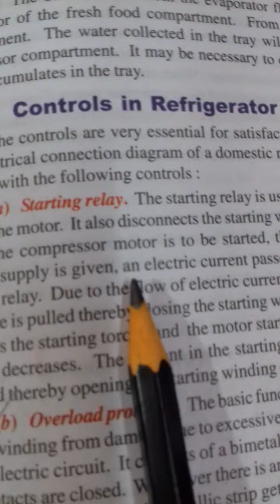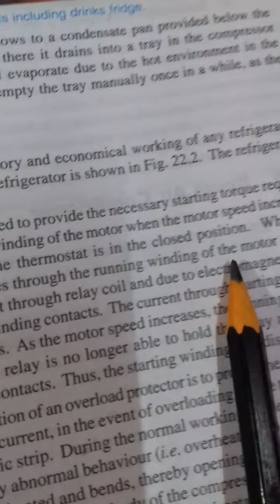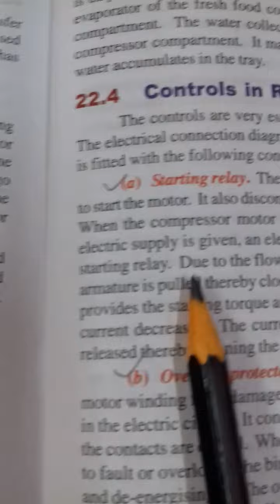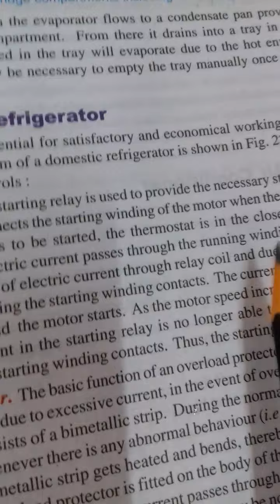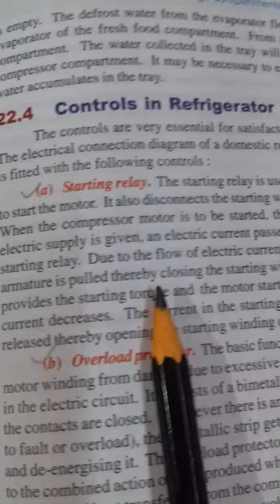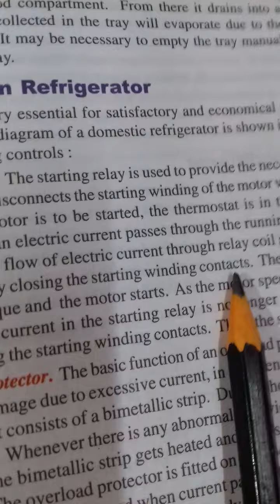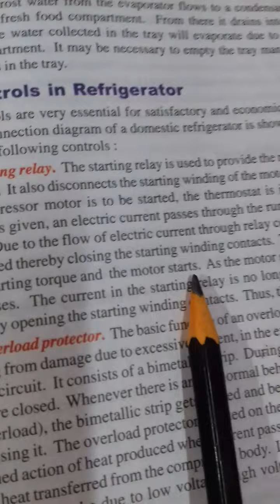When the compressor motor is to be started, the thermostat is in the closed position. When the electrical supply is given, an electrical current passes through the running winding of the motor and the starting relay. Due to the flow of the electric current through the relay coil and due to electromagnetism, its armature is pulled, thereby closing the starting winding contact. The current through the starting winding provides the starting torque and the motor starts.